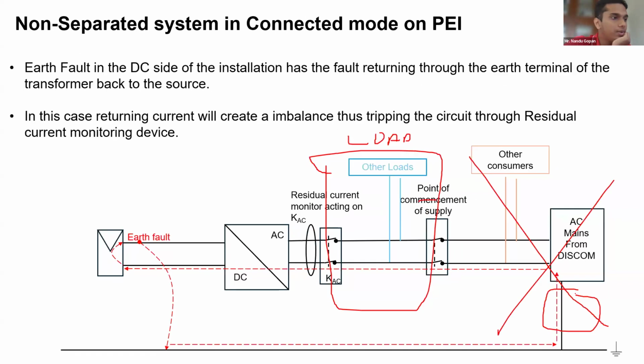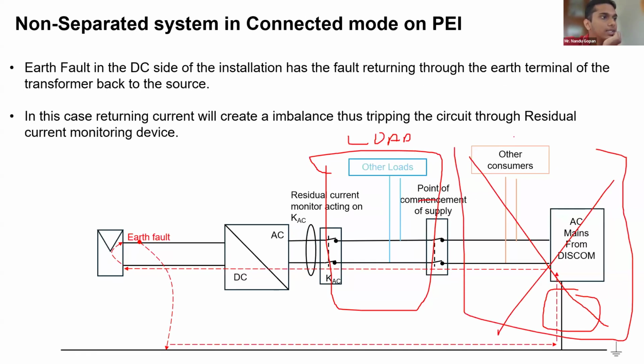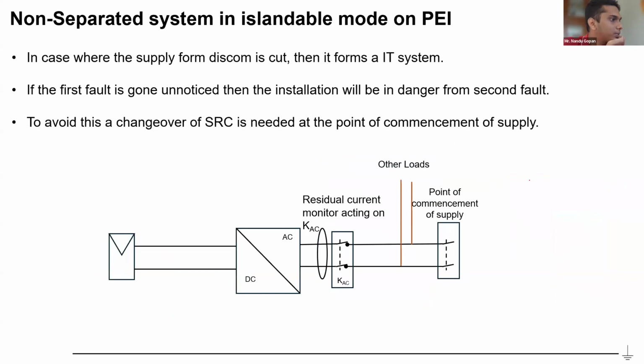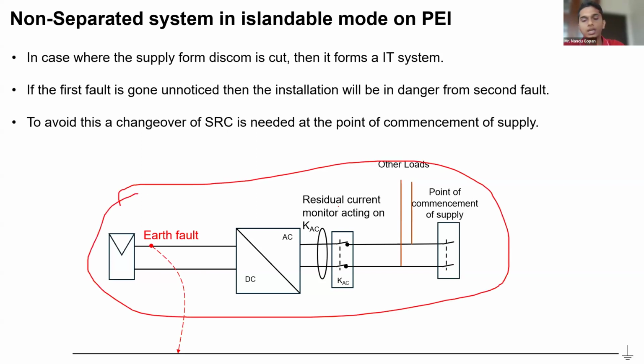I have removed this from this area in the next slide. So in that case, if there is an earth fault in the PV side, since this is a TT system, there won't be any system referencing conductor. You won't be doing it at the point of commencement of supply, only in the discom's transformer. So this becomes an IT source, an IT system referencing. So the consumer or the prosumer won't be able to find that there is a problem in this system, an earth fault in the solar PV side.